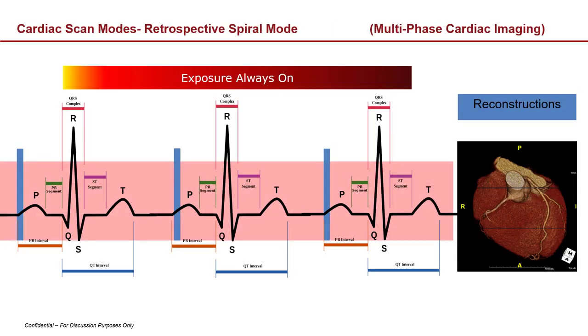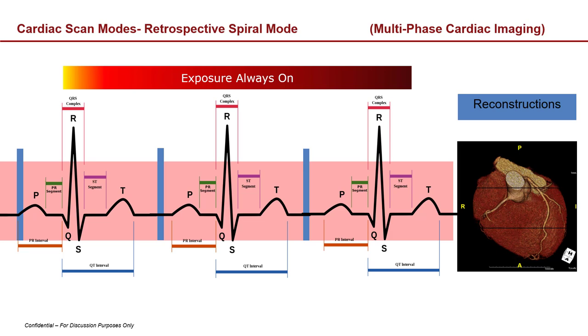The main way we use cardiac gating is in retrospective spiral mode — multiphase cardiac imaging. This allows taking pictures from any one of these beats. The red area represents radiation exposure to the patient; the blue area is the actual reconstruction. We're applying a lot of x-rays but only using a fraction of that data. Historically this made coronaries a high-dose procedure. In retrospective gating, the table translation must capture a whole heart cycle before moving to the next portion, synchronized with the ECG — moving slowly for low heart rates and faster for high heart rates.